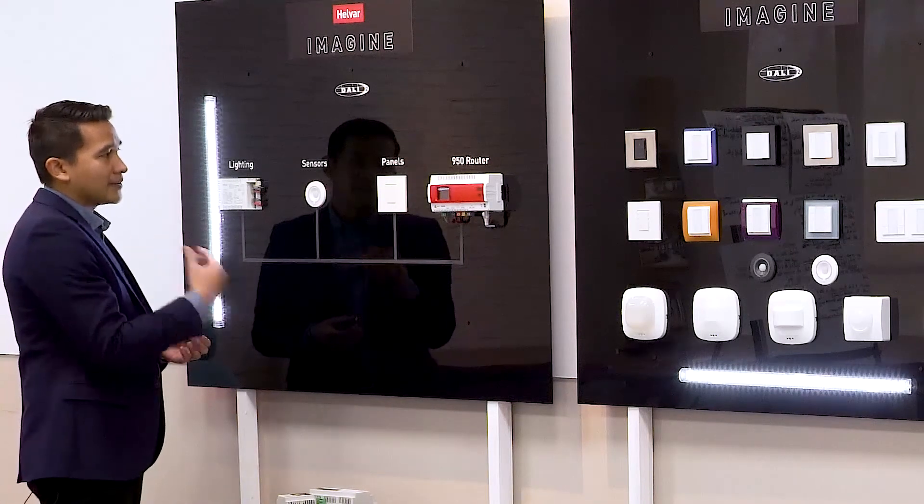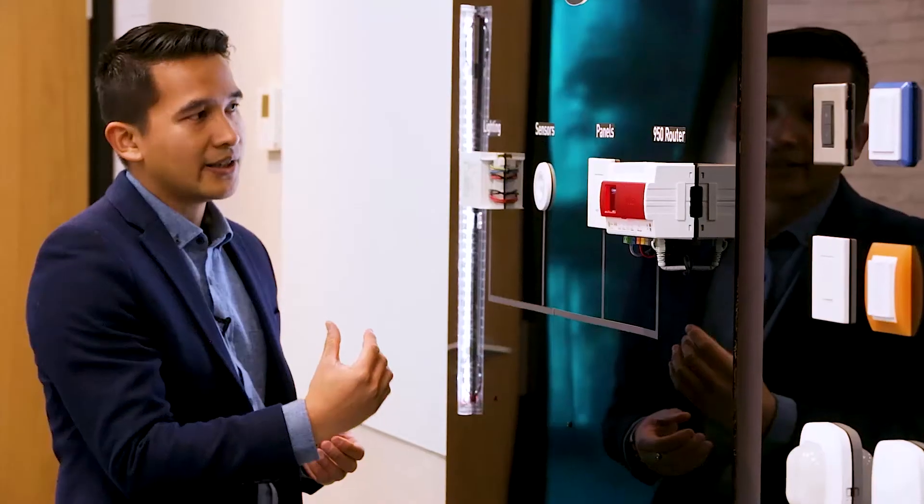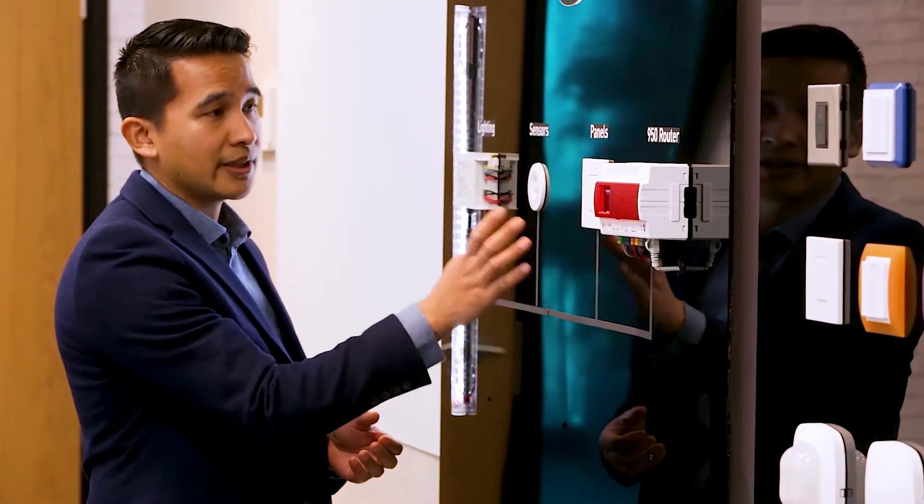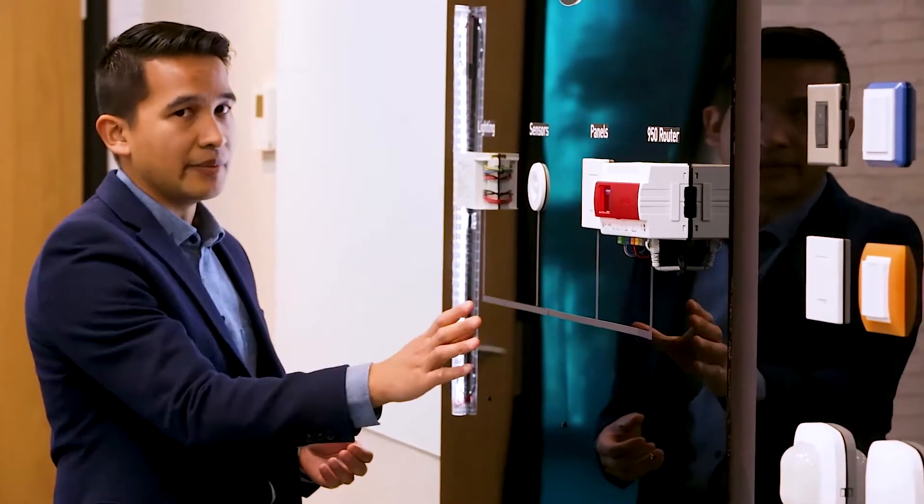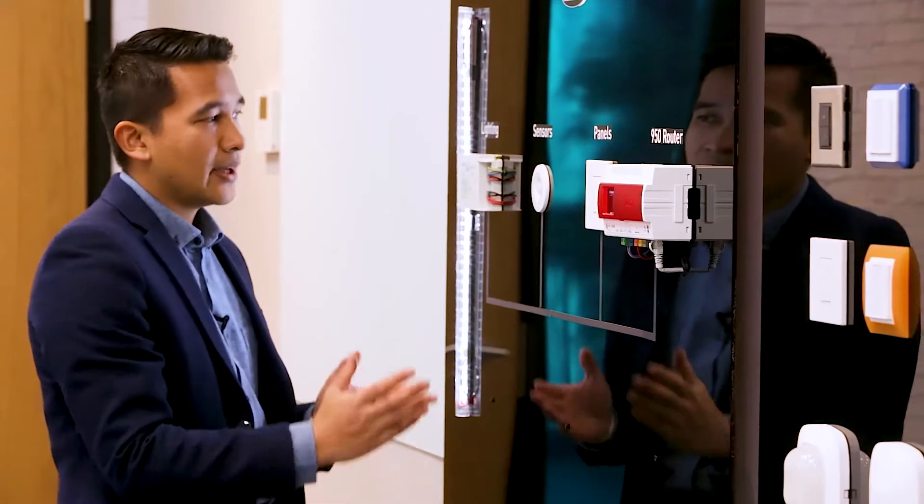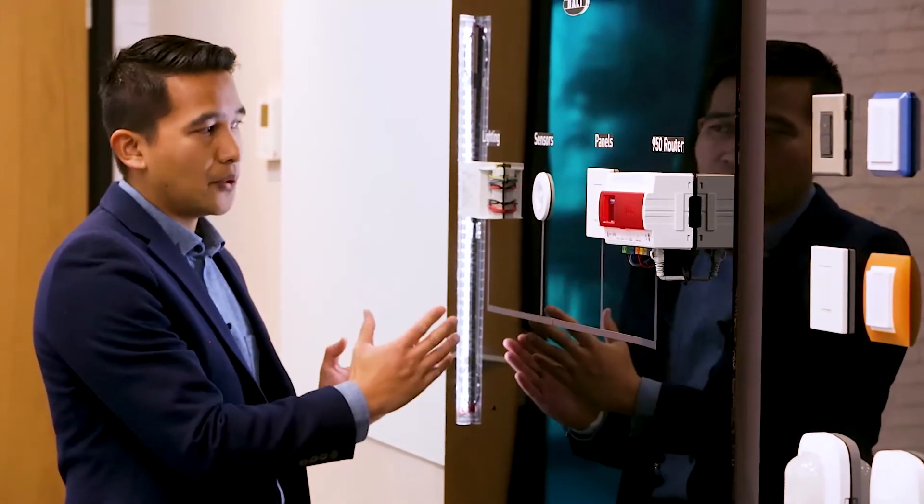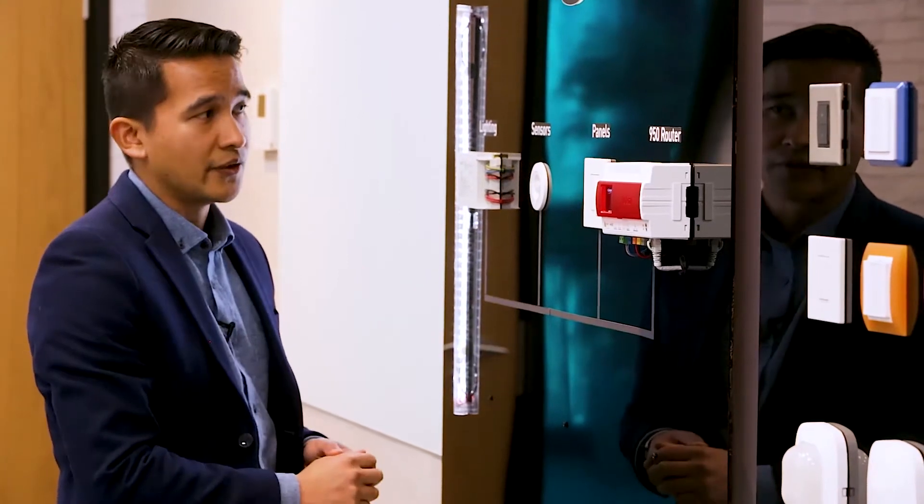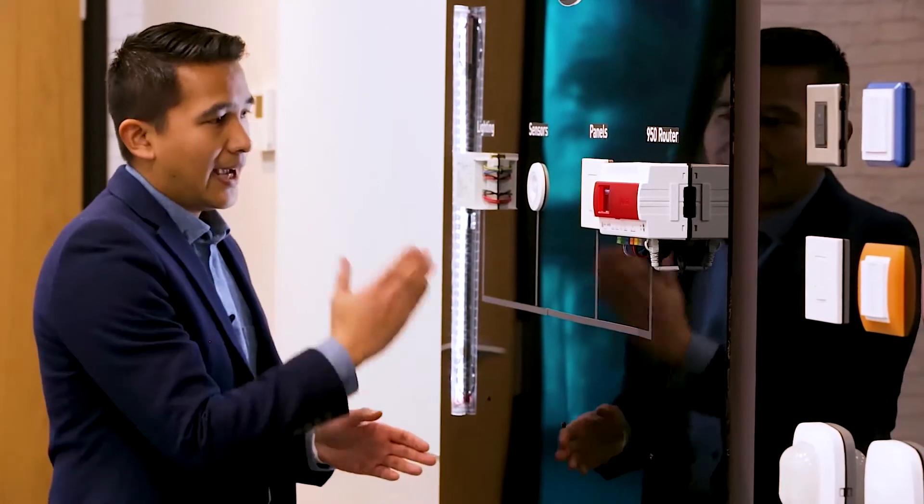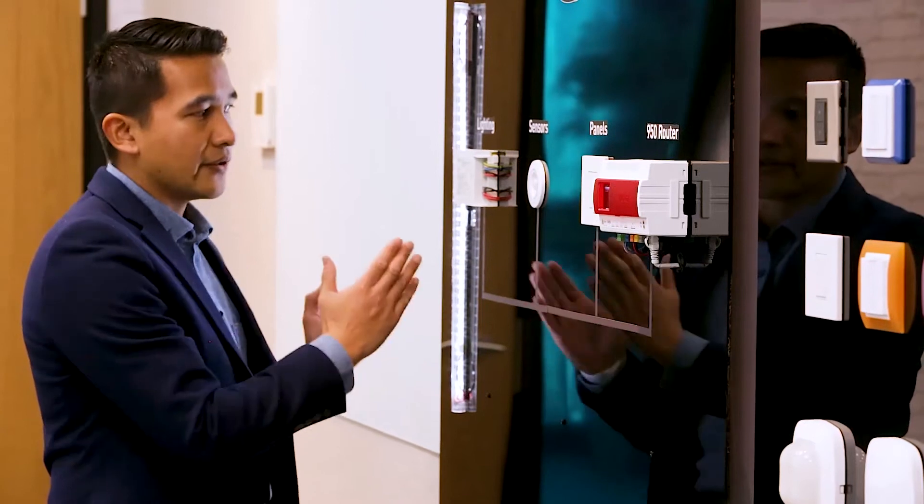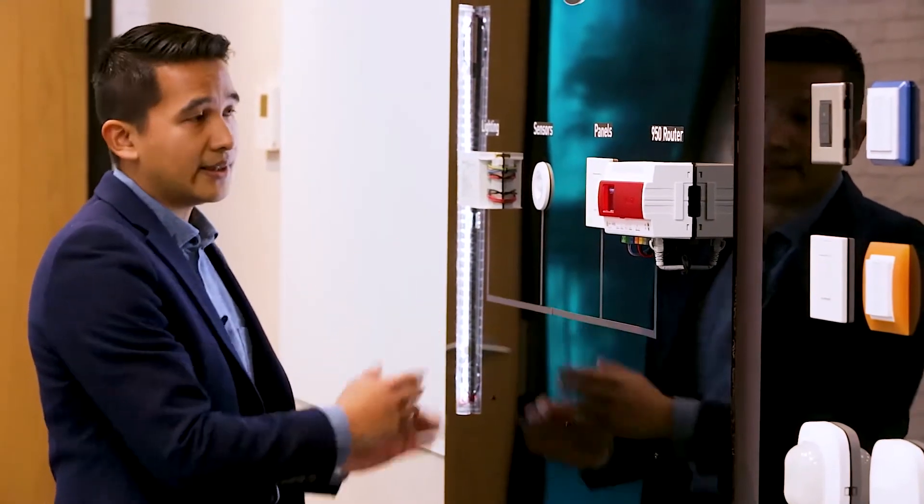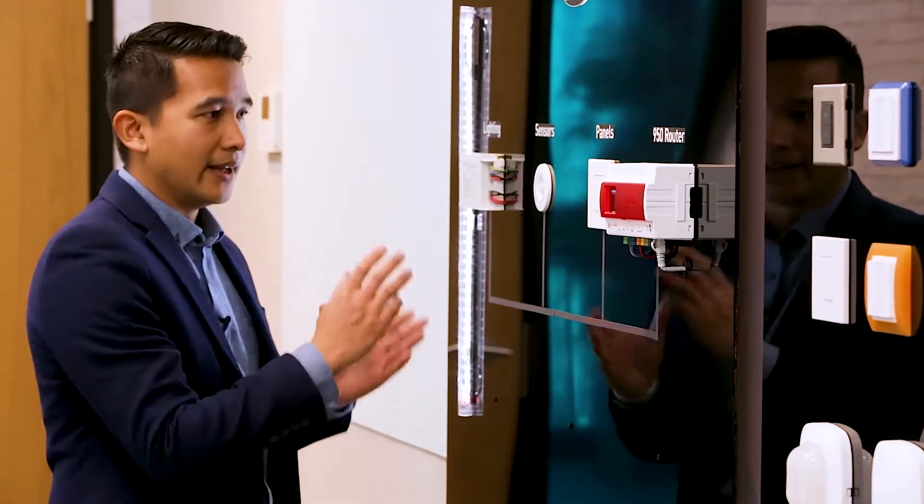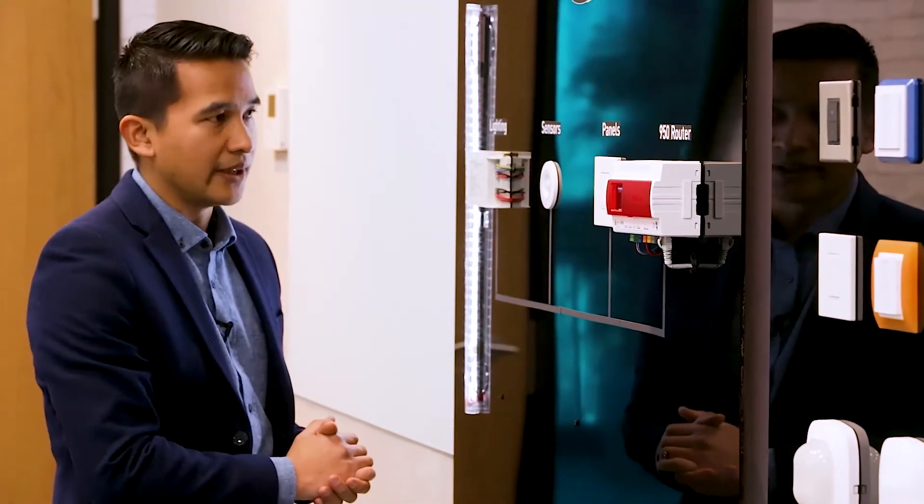One thing that has been added with DALI 2 is an additional 64 addresses for lighting controls products or lighting control devices on the same network. So essentially now you have a software limit of 64 addresses for your control products. And it is a hard division here of 64 and 64. You cannot have 65 lights and you cannot have 65 sensors and panels.